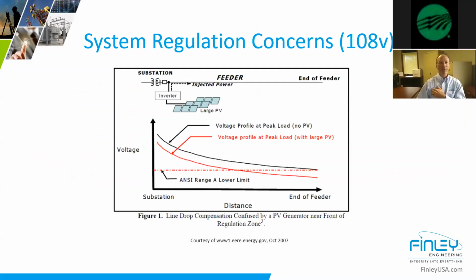Okay, so here I have an example for you. And we're going to talk about voltage regulation first. We'll come back to system protection. So you look at this example, and here at the top, I've got a typical feeder, and you've got the substation. And in this example, we're injecting a PV source close to the substation. So if you look at my graph here, I'm showing the ANSI lower limit. I mean, typically the ANSI range is like 108 to 126. That's what we use to carry our substations, knowing we've got to compensate for getting all the way out to the end of the feeder with adequate voltage.